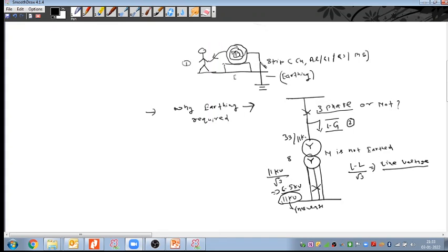Sir, if in place of a line to ground fault a three-phase fault occurs, then definitely the incomer feeder, the 33 kV feeder, I mean the bus bar, will sense it, no matter whether earthing has been done in the transformer or not. Correct.